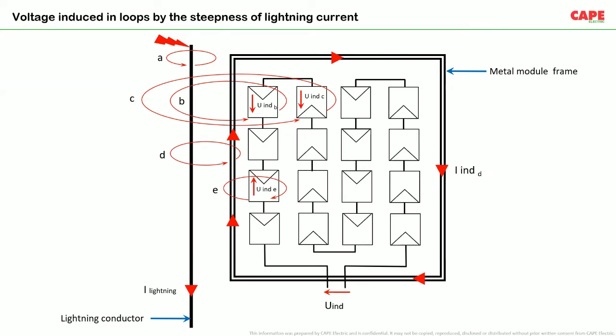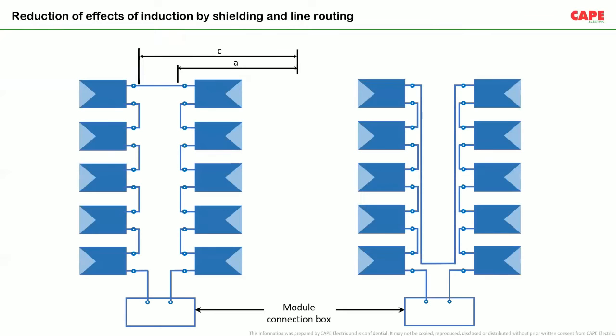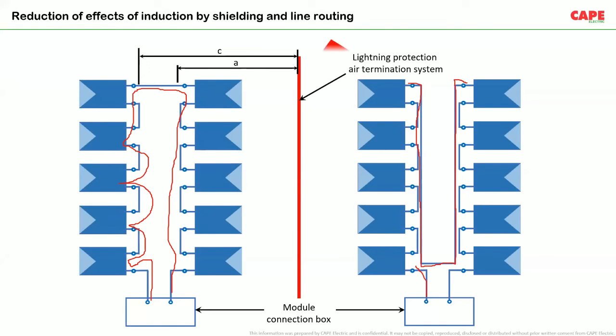For example, here there are two types of wiring shown. You see here, in the first case, from the combiner box the positive is coming, it is looped to each and every module, then it is coming back like this. In the second case, you see the wiring is made in such a way that the loop is reduced to a very small extent. So in this condition, if there is a lightning strike, voltage is created in the combiner box, and in the first case, due to the large loop, a high voltage is created in the combiner box, which may result in the failure of the PV system.